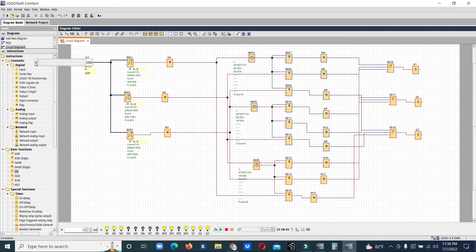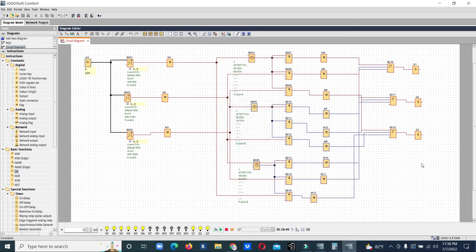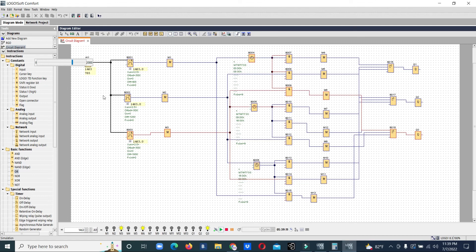When the cycle changes and the time changes, the first batch has come. Now we will check with the first batch. All pumps are running. Now pump one stopped, then pump two stopped, then pump three stopped. So in the last batch, pump two was running till the end. Now in this batch, pump three is running till the end. In the next batch it will change accordingly — this is the cyclic rotation working.